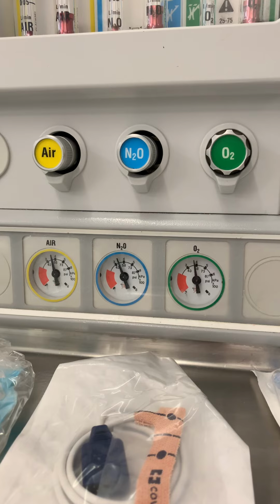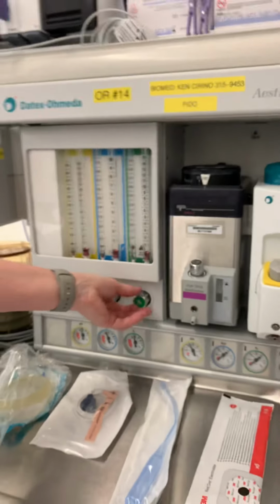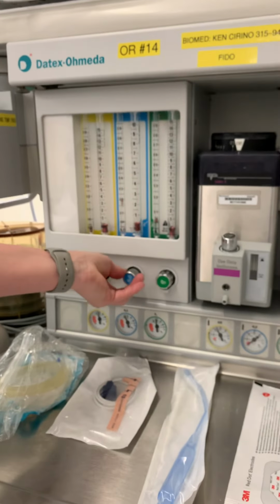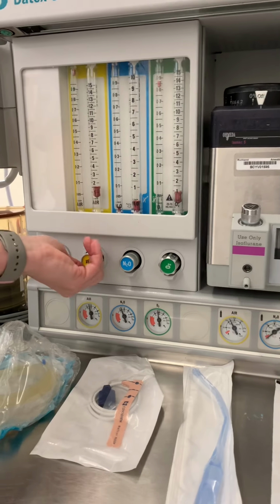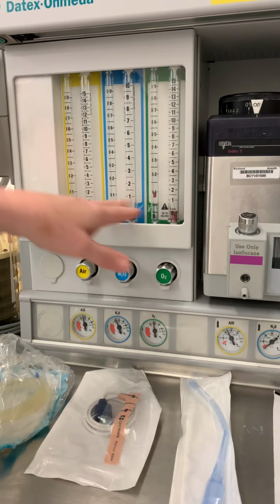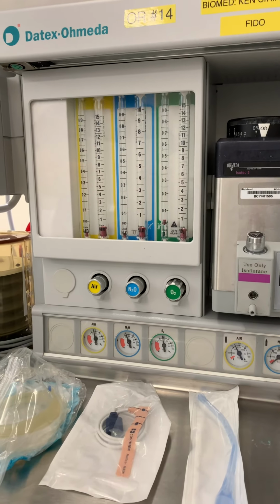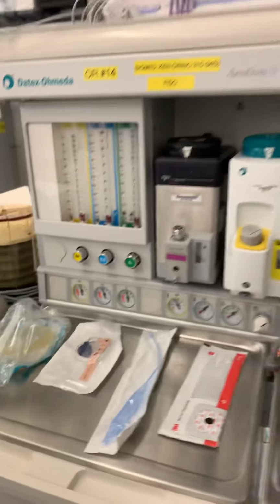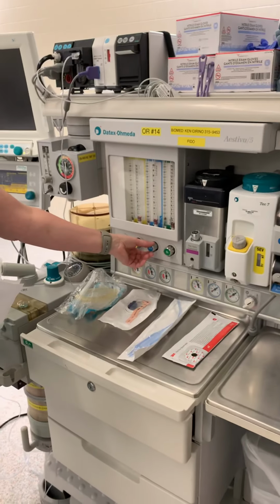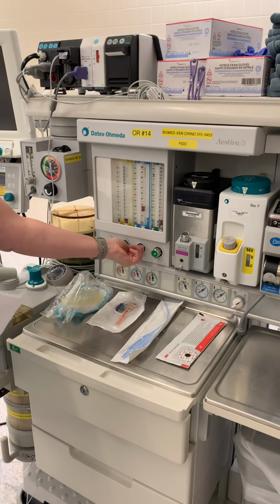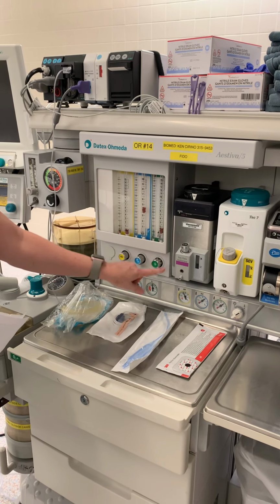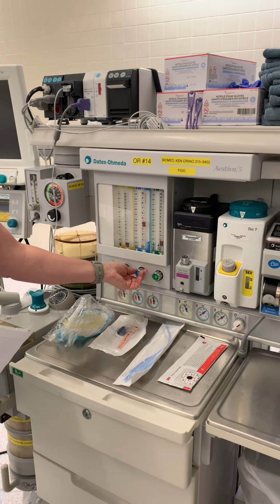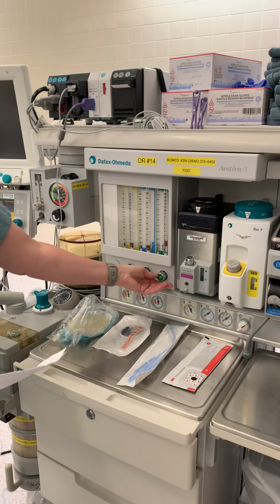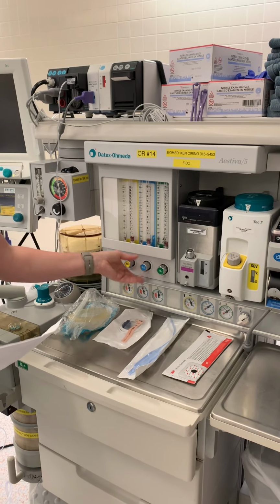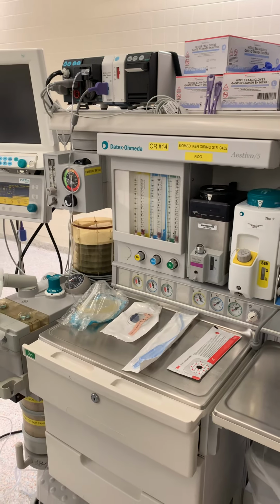We want to make sure that the flow meters are all functioning properly, that when you turn them, they actually do turn on and off, and they do, so your flow meters are functioning properly. We already tested the proportional system, but again, that's just where if you turn on the nitrous, it will proportionally turn on oxygen so that you do not deliver a hypoxic mixture. And now we're going to make sure that all the flow meters are off.